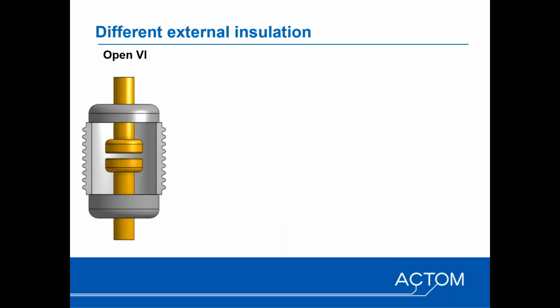Now, in terms of air-insulated circuit breakers, the vacuum interrupter is exposed to normal atmosphere. When the vacuum interrupter contacts are closed, the external insulation surface is effectively short circuited by the contact, so there's no leakage current flowing over the surface. But once the vacuum interrupter opens up, you effectively have the external creepage on the outside of the vacuum interrupter that now needs to deal with the effect of pollution. Because your vacuum interrupter is directly exposed to the atmosphere, you need to make sure that it's got enough creepage over the surface to deal with the effect of leakage current.